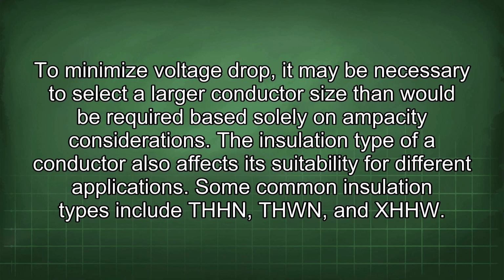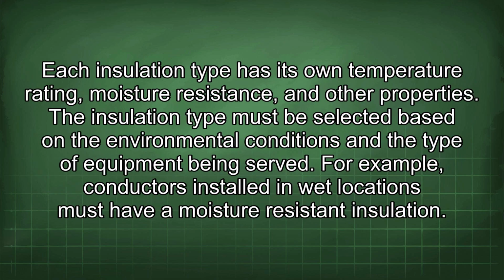Some common insulation types include THHN, THWN, and XHHW. Each insulation type has its own temperature rating, moisture resistance, and other properties. The insulation type must be selected based on the environmental conditions and the type of equipment being served. For example, conductors installed in wet locations must have a moisture-resistant insulation.